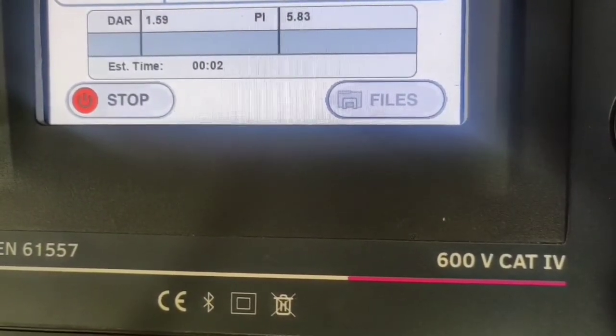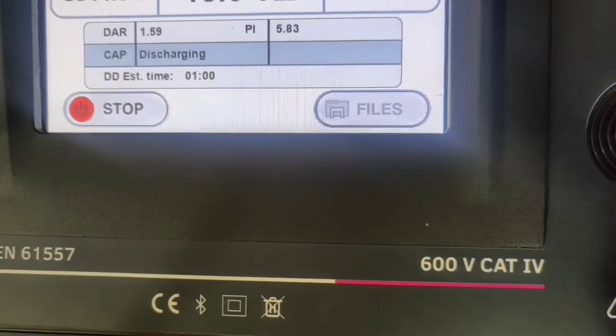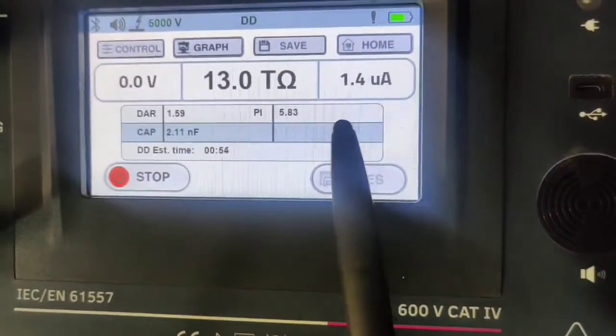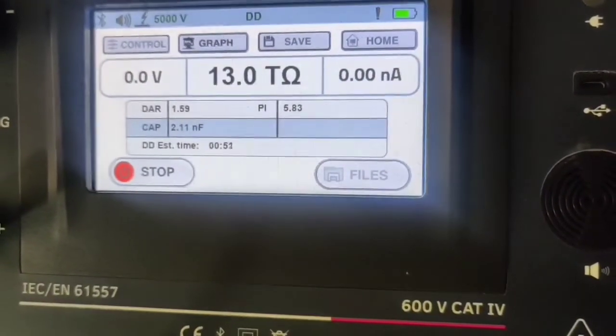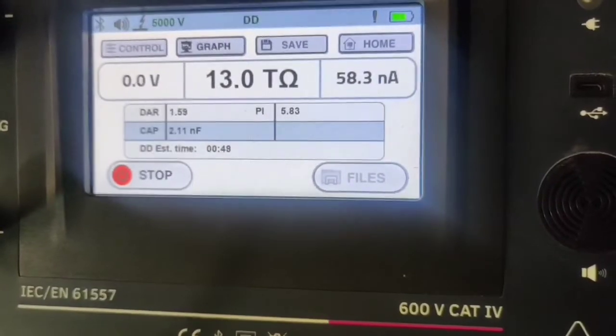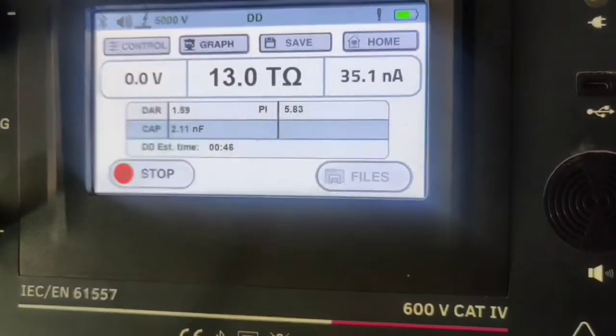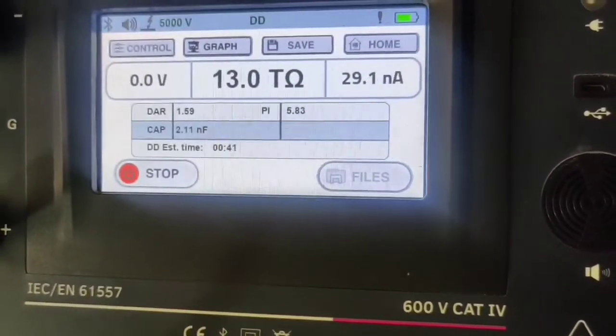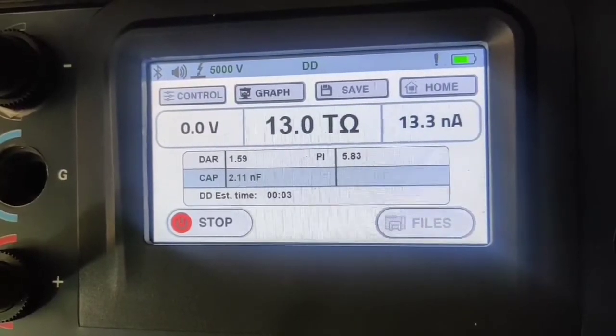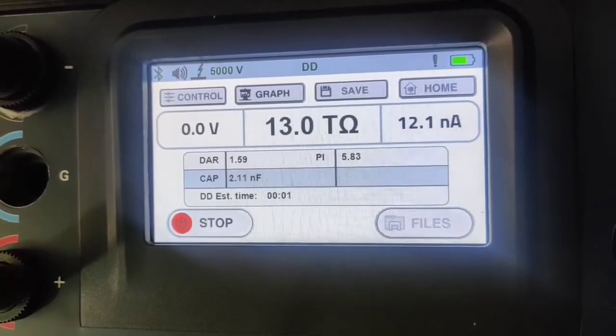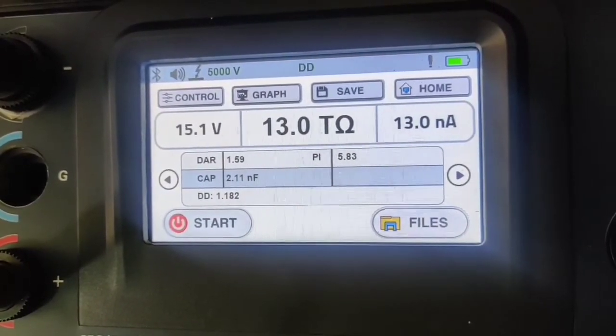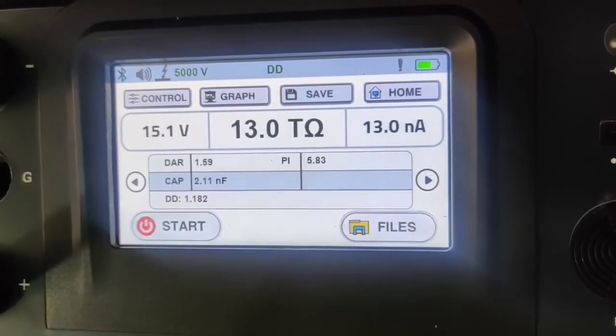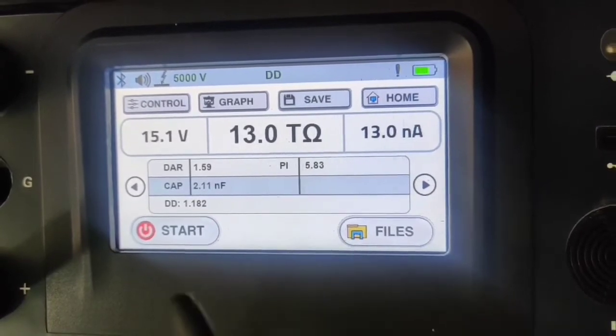After completion of the 30-minute test, the discharge current test starts for 1 minute, during which the discharge current is measured. After completion of the discharge current test, the unit will automatically calculate the DD value using the formula: current after 1 minute divided by test voltage multiplied by measured capacitance. The DD test has been completed, and the measured DD value is 1.182.